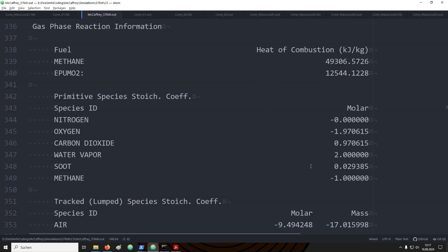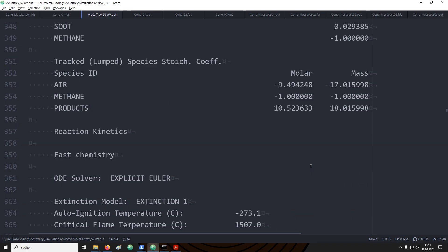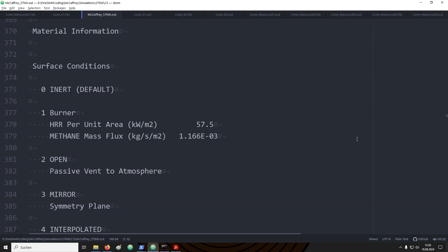After the mixtures, information about the individual gas species are provided, and also more detailed information about the lumped species, for example, the air. Details on the gas phase combustion reactions are available as well. For example, which fuel was used and its heat of combustion. We will look at this again when we talk about the heat release rate that we wanted to set up for the gas burner. FDS also provides the stoichiometric coefficients. These have been determined during the simple chemistry that FDS uses for the combustion in its default setup.